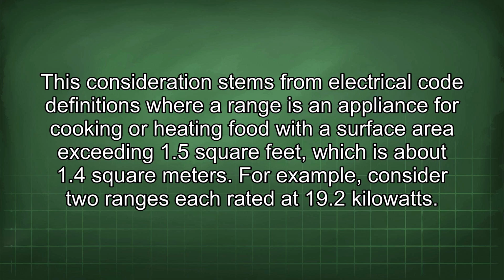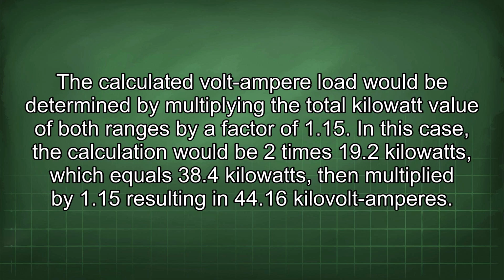For example, consider two ranges each rated at 19.2 kilowatts. The calculated volt-ampere load would be determined by multiplying the total kilowatt value of both ranges by a factor of 1.15. In this case, the calculation would be 2 times 19.2 kilowatts, which equals 38.4 kilowatts, then multiplied by 1.15, resulting in 44.16 kilovolt amperes.